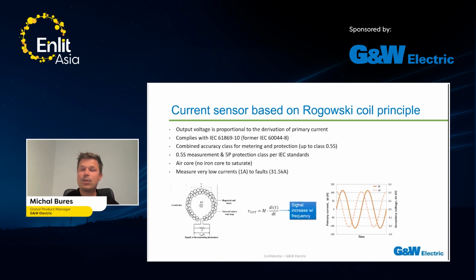Current sensors, as I mentioned, are based on the Rogowski coil principle, which is, I would say, one of the most common solutions on the market. The output voltage is proportional to the derivative of the primary current. So yes, the output of the current sensor is voltage. It also complies with the newest IEC standard. You have again, as for the voltage sensors, a combined accuracy class for metering and protection, so you can do both measurements at once. 0.5S accuracy class, and you have no iron core inside.